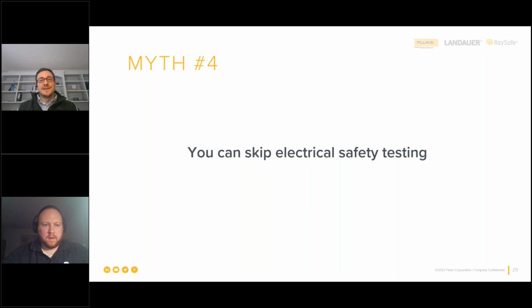But think about what that medical device goes through on a day-to-day basis. Is it wheeled over bumps? Is it dropped or tipped over? Does it ever experience environmental conditions it shouldn't, like humidity or temperature? And even on incoming inspection, when a new medical device arrives at your hospital, do you inspect it to make sure it wasn't damaged during shipping, or are you just trusting that it maintained the manufacturer's specification from the factory to your facility?